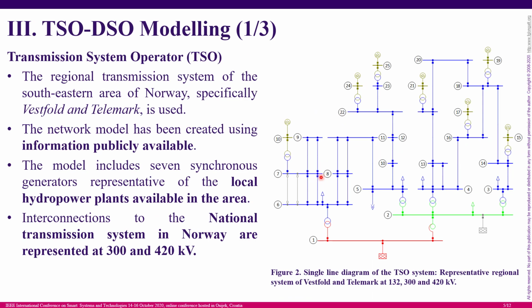In this paper, we are using a combination of a transmission system and a distribution system. For the transmission system, we are using an equivalent model. This is a 132, 300, and 420 kV representation of the regional network in the Vestfold and Telemark area. This network has been created using publicly available information, and it includes synchronous machines for representing the hydropower plants available to the loads in the area. Also, the national transmission system at 300 and 420 kV has been modeled as external grids.